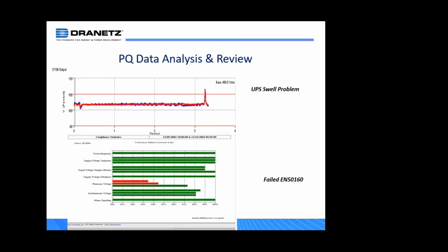And then, of course, if you're monitoring equipment itself, is the equipment performing as it should? A very common application that we see is what we call UPS monitoring. And UPS monitoring basically deploys two monitors, one at the input of the UPS, the other at the output of the UPS. And there are a number of things that you're looking for there.